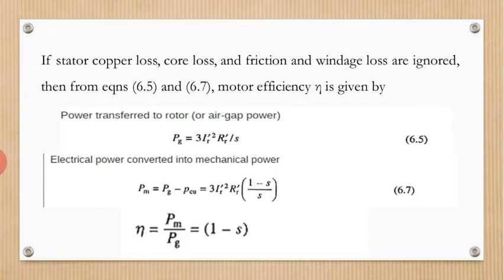Hence the efficiency is not only low, the power dissipation also occurs in the rotor itself, which overheats the rotor. Because of these reasons, these drives are employed only for fan and pump drives of low power rating and for a narrow speed range.